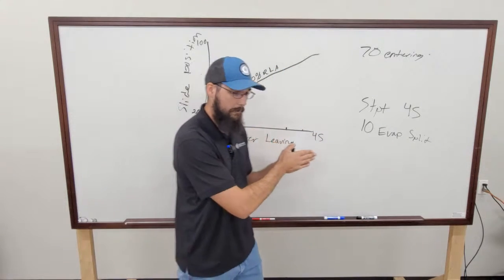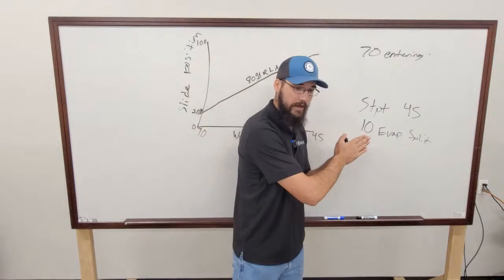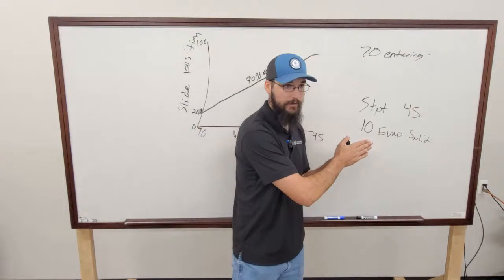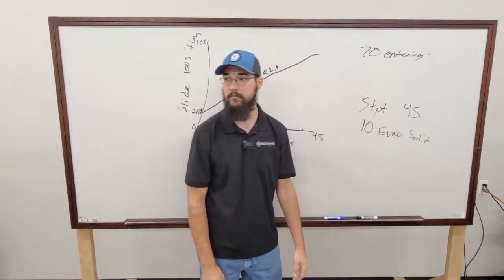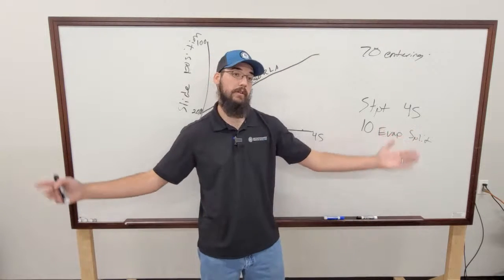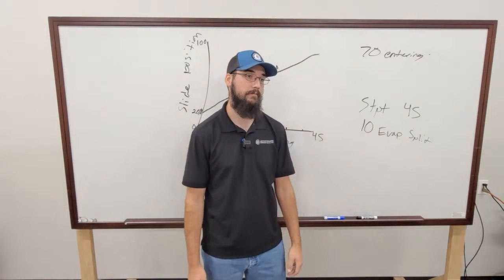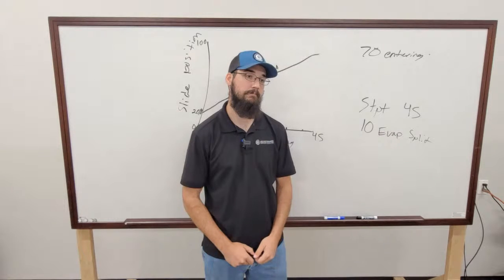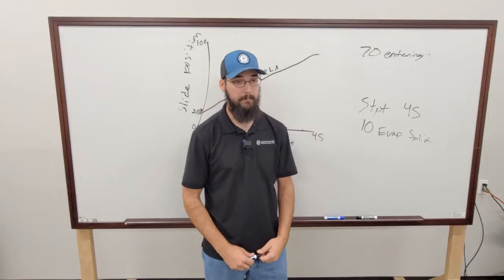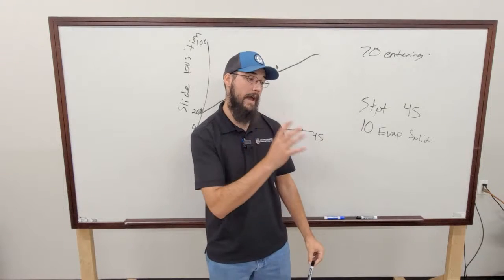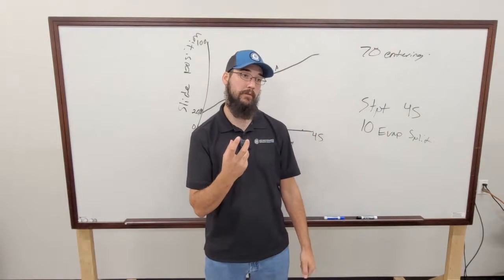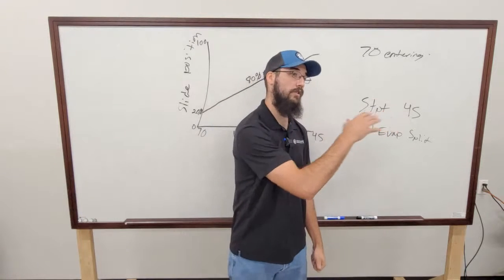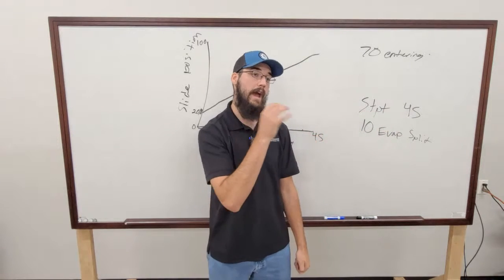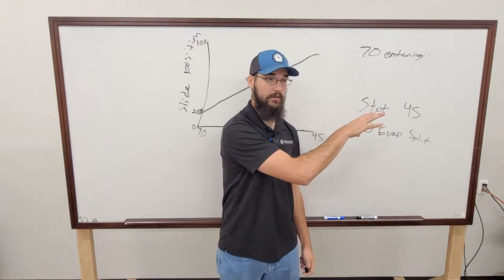Okay, pull down. Once we've satisfied the pull down parameters, we just go back into normal operation. And until something crazy happens, it's just going to run. And it'll release that current limiting at that point? Yes. It'll come out of the current limit set point for pull down and default to whatever the actual current limit is on the machine.